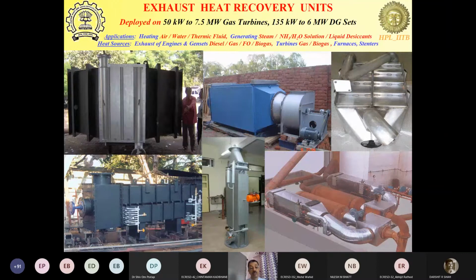And this was, of course, for steam generation in this particular example. And we had multiple modules of these. Then we have also done gas turbine exhaust heat recovery systems, right up to 7.5 megawatt exhaust heat recovery. And our system was 1/3 the size of the conventional internationally accepted norm. We are heating thermic fluid from 230 degrees to 250 degrees in this case using the gas turbine exhaust.